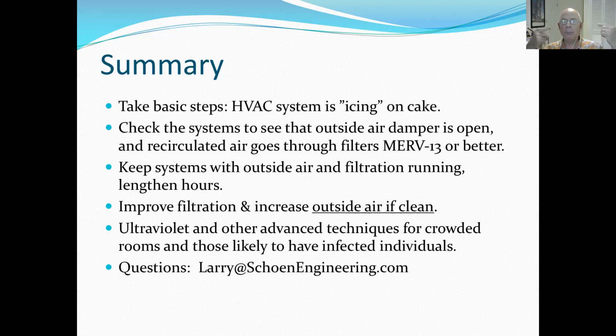Don't think you need a HEPA filter for your central air handler. Not only don't you need it, your system probably can't handle a HEPA filter, and you probably don't want to spend the money for it. The MERV 13, 14, 15, 16, if you can go even higher, depends on the thickness of your rack and what you can get commercially available. That's good enough for a central air handler. For those little room air handlers, they're trying to turn over a lot of air and do a good job in the room. Those are sized for the pressure drop to handle the HEPA filter.